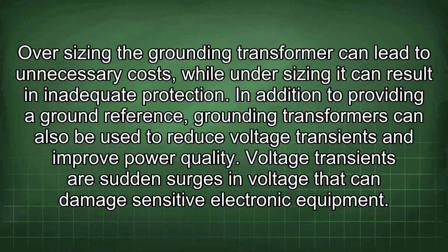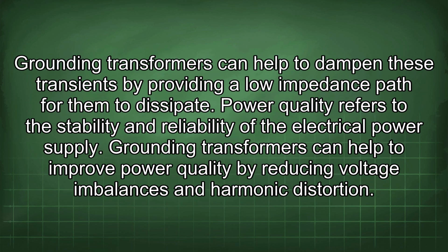In addition to providing a ground reference, grounding transformers can also be used to reduce voltage transients and improve power quality. Voltage transients are sudden surges in voltage that can damage sensitive electronic equipment. Grounding transformers can help to dampen these transients by providing a low impedance path for them to dissipate. Power quality refers to the stability and reliability of the electrical power supply. Grounding transformers can help to improve power quality by reducing voltage imbalances and harmonic distortion.